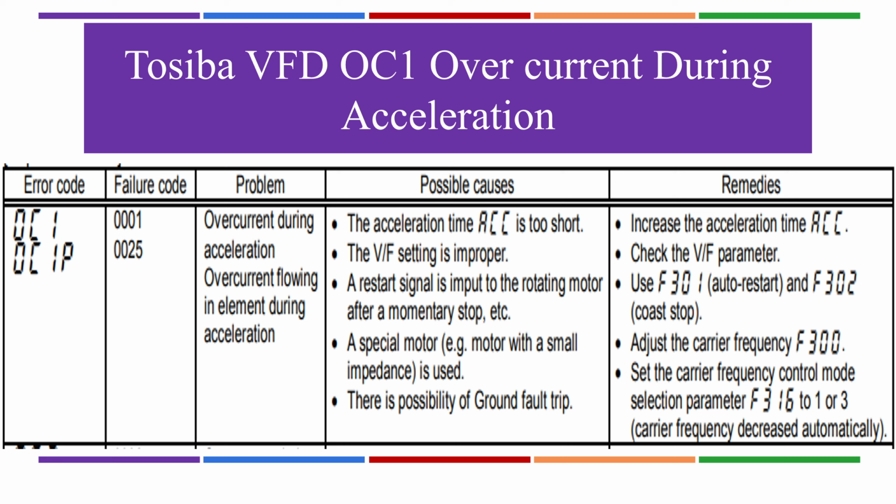There are the acceleration and deceleration times in the VFD. So we need to check if the acceleration time is too short, and this is normally the reason. Sometimes it could be that the motor has very small impedance, or that a ground fault has tripped it. There is the possibility of a ground fault trip. So we need to increase the acceleration time.